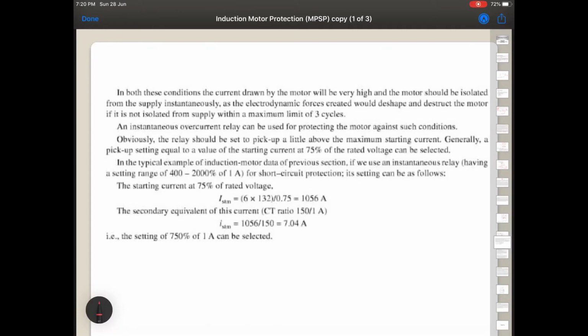Now an instantaneous overcurrent relay is used for protecting against the two conditions which we have seen, the short circuit condition and the blocking condition. The instantaneous overcurrent relay works basically on the principle that it checks whether the current is higher than the set value, and if so, it will simply operate. So here the pickup setting is a value of current at 75% of the rated voltage.